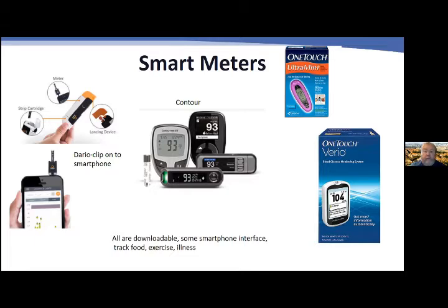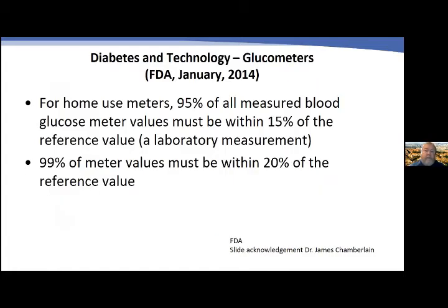If patients enter all different kinds of data, you can get a very easy-to-read comprehensive overview of what's been happening — much better than a traditional paper logbook. About six years ago, the FDA issued guidance to improve meter accuracy: 95% of all measured blood sugar values must be within 15% of the reference, and 99% must be within 20% of the reference.